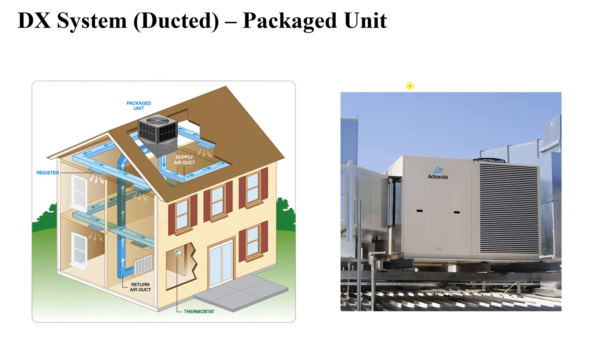There is also a package unit, which contains all components together in one block. It is usually placed on the rooftop and supplies cold air through the duct system. A return air duct absorbs warm air from the building and brings it back to the evaporator, which exchanges heat and provides cold air. These are all the different types of DX systems, all operating on the same principle of compressing and expanding a refrigerant.